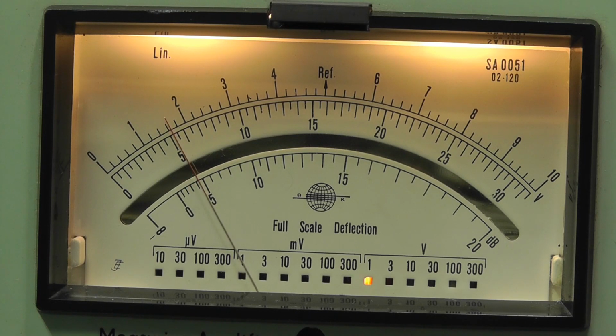It's a fairly fine sweep here. We're doing it basically, the analyzer does in steps frequencies. It steps to the next frequency, measures it, steps to the next frequency. We're now at 100 Hertz. You see the gains rapidly coming up. It'd probably be better if I did it on a dB meter, but you can see it's basically back to flat at 400 Hertz now. And looking at the chart here, we've got a nice low frequency roll off. You see the levels are staying pretty flat, and eventually I expect to see the level falling away again.